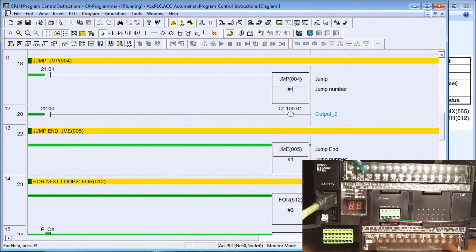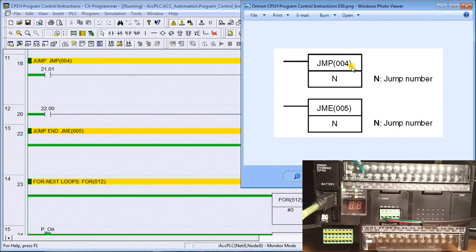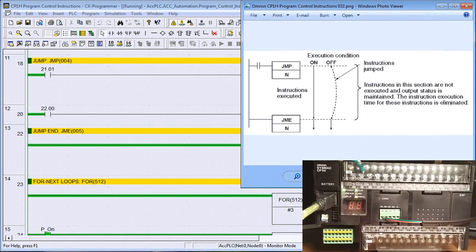The next instruction we're going to look at is the jump instruction. We have a jump to a jump number, and then we have a jump end which signifies the end of that jump. When the condition is on, the instructions are executed normally. When the condition is off, that causes the jump and the output status is maintained — meaning your program is not being scanned anymore, so outputs will maintain their last state unless activated somewhere else.